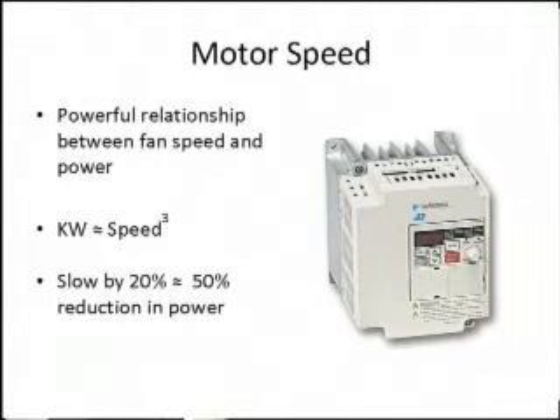Power is fan speed and pressure drop. So this takes advantage of the fan speed part of it. And it's a cubic relationship, as you can see here. So if we can drop a fan speed by just 20%, that translates to a 50% reduction in power for us. This is much more powerful than even the filter thing is. And if we take it to 50%, which we routinely do at night in our facilities, overnight we might be down in the 50s. 50% translates to an 87% power reduction for that motor.